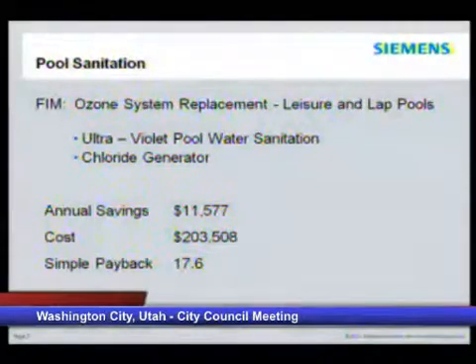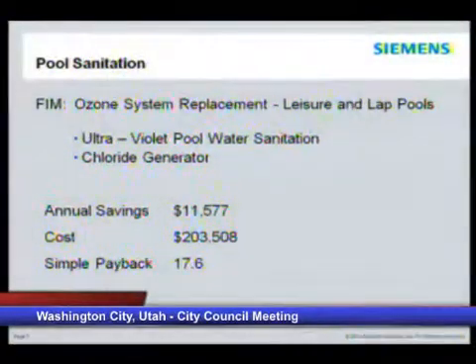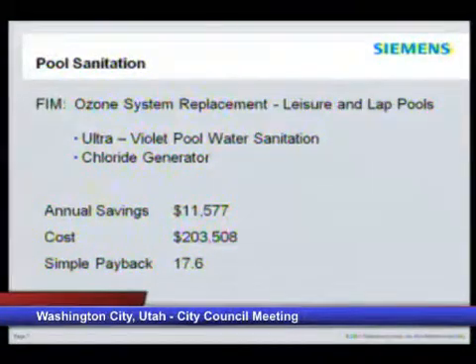And when you get cryptosporidium, which is the most hard to kill, even in chlorinated pools, it may take as many as 10 days to kill. That's just reality, even in well-maintained pools. These secondary systems, such as ozone and UV, kill it on contact, essentially disable it. So that's why it's required. If you do not have a UV system under the current code, and there were a cryptosporidium outbreak in southern Utah, the health department could come in and say you've got to superchlorinate your pool a minimum of 2 times a week for the extent of that warning period.